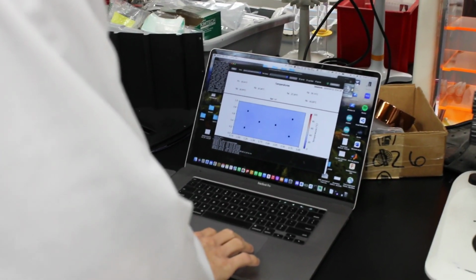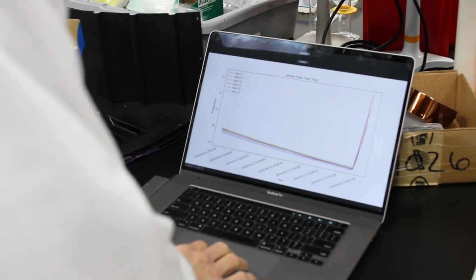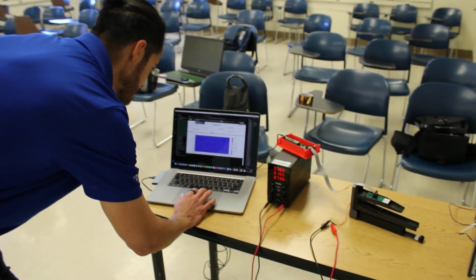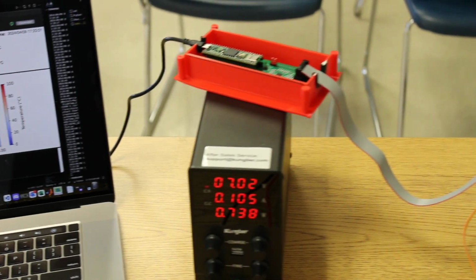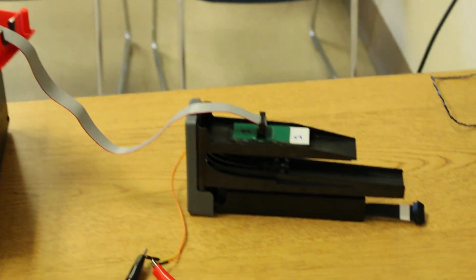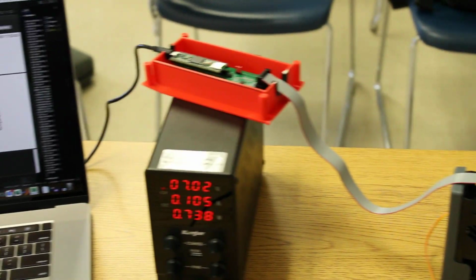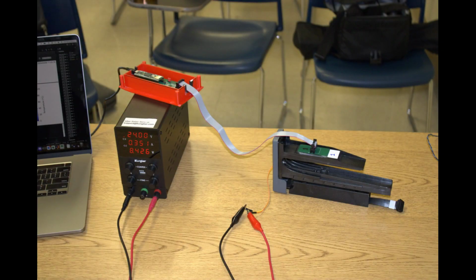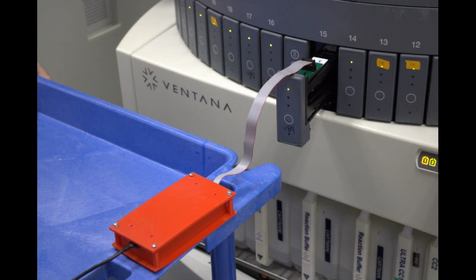Finally, that information is transmitted to the user interface where it is displayed on a thermal map of the glass slide. Our requirements were verified by either inspection, demonstration, analysis, or testing. Our system was designed to meet all of our functional requirements, such as employing 6 total thermistors and designing the system to be simply 2 major, durable sections that can be moved around from machine to machine. The size and shape of our device was also designed to integrate easily with the Benchmark Ultra and provide easy use for technicians.